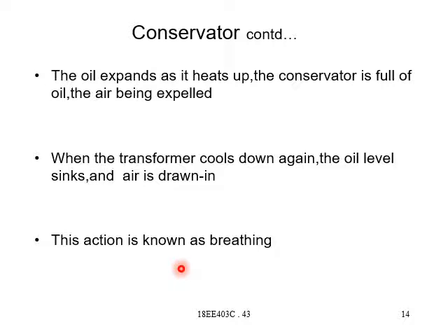In and out, we can see that the oil expands during heating. During heating, any material will expand, thereby the conservator is full of oil. In the initial state we won't fill the conservator tank completely, we'll partially fill it, and during heating it expands and completely fills up the conservator, and the air being expelled, that is the left out part which has some air in it, is expelled out to the atmosphere.